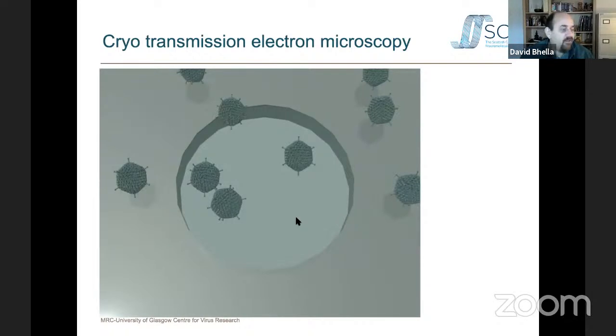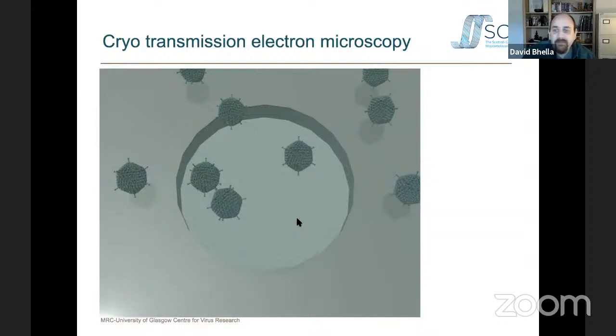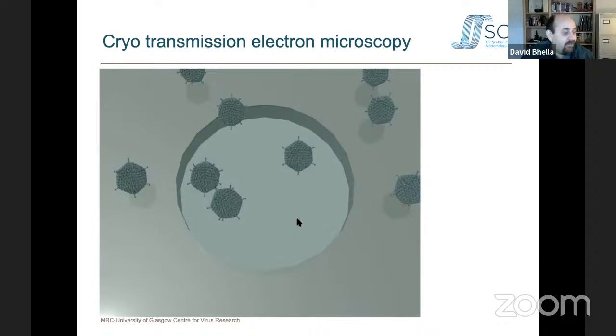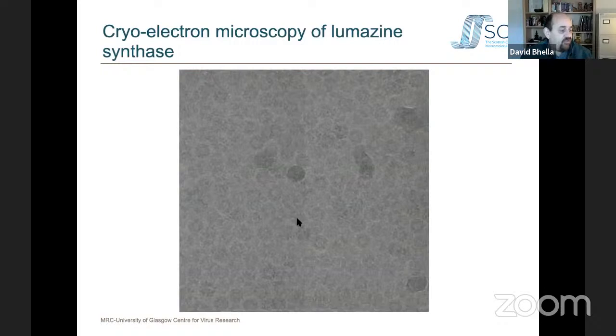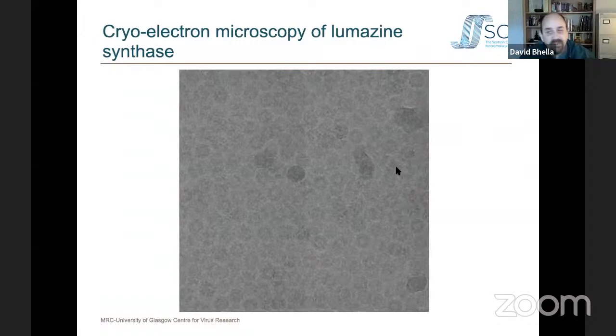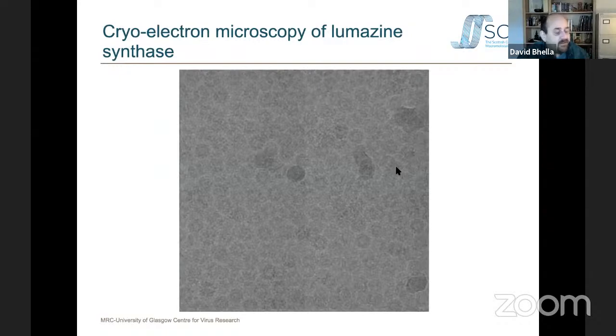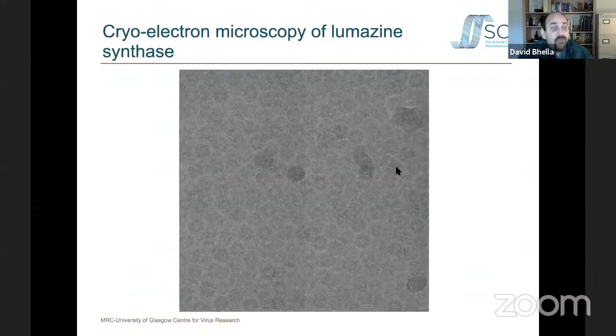We blot the sample to make a thin film of maybe 100 or 200 nanometers thick, which is rapidly frozen by plunging into a cryogen such as liquid ethane or an ethane-propane mix. What results is a thin layer of glass-like ice in which our object of interest is suspended in random orientations. This is then transferred into the transmission electron microscope for imaging without stain and without drying — effectively taking something in aqueous suspension, turning that water solid, and imaging it unperturbed.